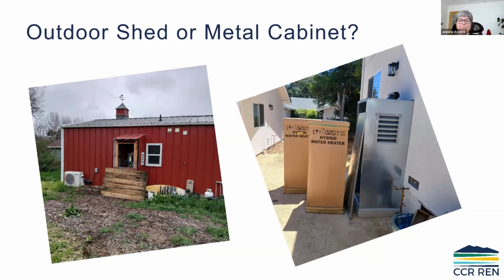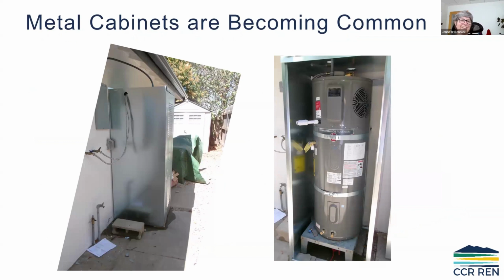And then the slide after it is totally funky - go to that one again. If you look at it, the hot water and cold water piping is coming out through a hole into what looks like a hose bib fitting, and it's not insulated. There's some room for improvement, even though they did get the spacing right. And the condensate is just horizontal piping to nowhere, which is going to drip - you can see water at the base of the cabinet on the left.